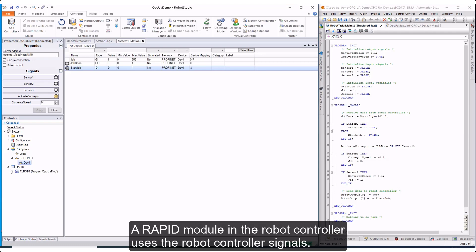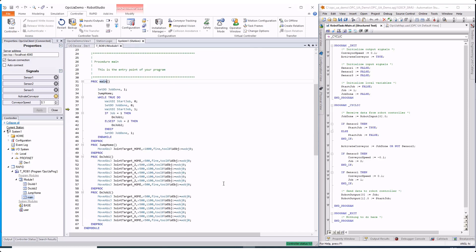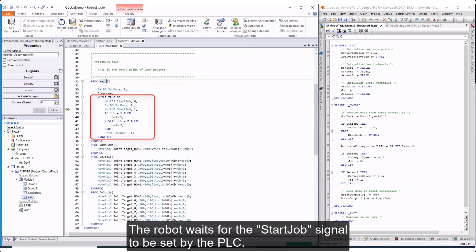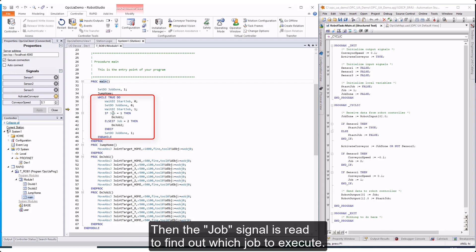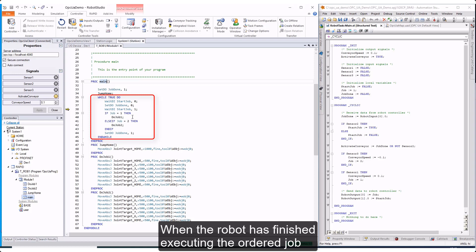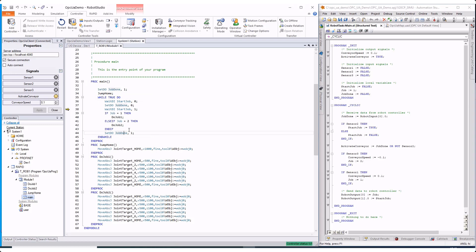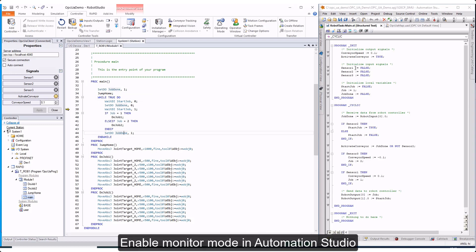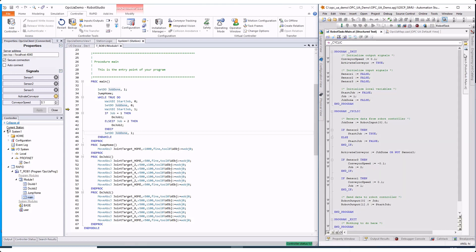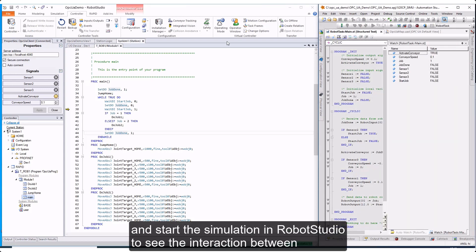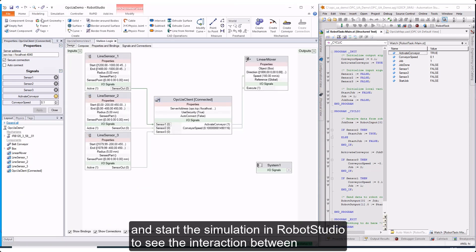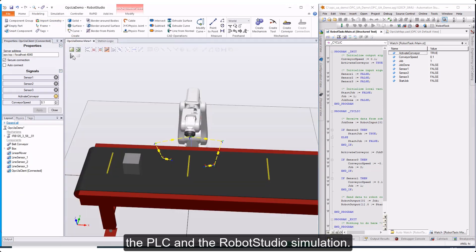The RAPID module in the robot controller uses the robot controller signals. The robot waits for the Start Job signal to be set by the PLC, then reads the Job signal to find out which job to execute. When the robot has finished executing the ordered job, it sets the Job Done signal. Enable monitor mode in Automation Studio and start the simulation in Robot Studio to see the interaction between the PLC and the Robot Studio simulation.